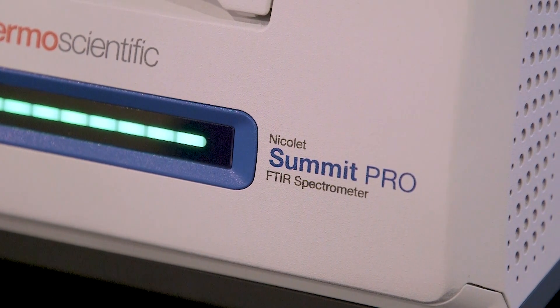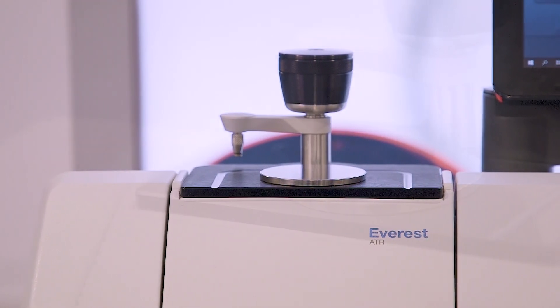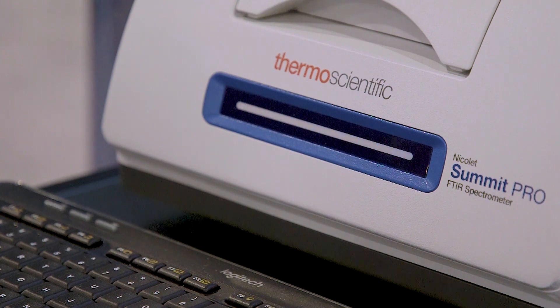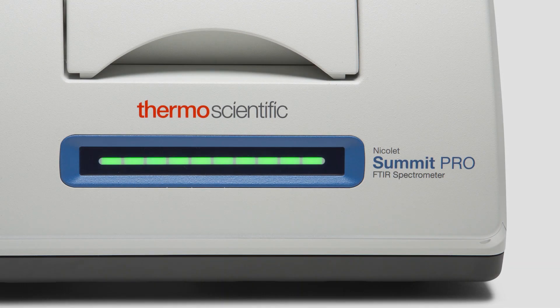The Thermo Scientific Nicolet Summit Spectrometer has been built with innovations to help users in QA, QC, and academic teaching laboratories work faster by really working smarter. On the front of the instrument is a multi-color LED light bar, which not only displays the instrument status and the health of the spectrometer, but it can also provide a quick visual indication of pass-fail results.